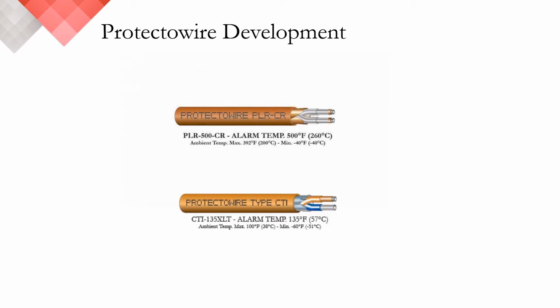As the leader in linear heat technology, we're constantly looking at areas to expand product capabilities. Two recent introductions are the perfect bookends to that endeavor, with the recent introduction of both our highest and lowest activating detectors to date, the PLR 500CR and the CTI 135 XLT. Both products address very specific needs within the marketplace. The PLR 500CR was developed to focus on applications that are constantly exposed to extreme temperatures, furnace work, kitchen applications, things of this nature. The CTI 135 XLT, along with its sister in our PHSC series, was brought about to address the extreme environments of industrial freezers and the ability to provide a pre-action system that will react before the sprinkler hits. Couple this with CTI technology and you have the perfect solution for the industrial freezers of all shapes and sizes.